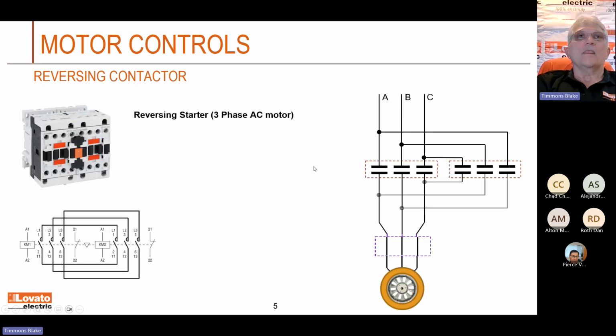Look at that. So here's a contactor for a reversing contactor I did. This is very common. To reverse the direction of a motor, you have to change any two wires in that three-phase circuit. You can see as I come in here, I feed on the right side the line side, the top side of two different contactors. But on the bottom, you can see where it switches those two. Let's get a little animation here. You can kind of see what I'm talking about.